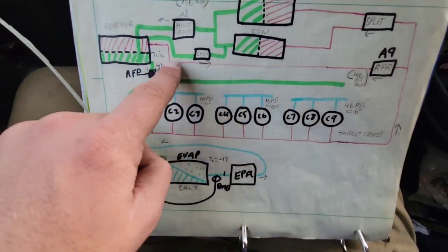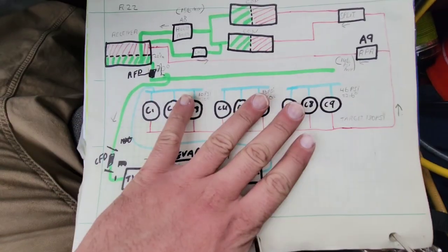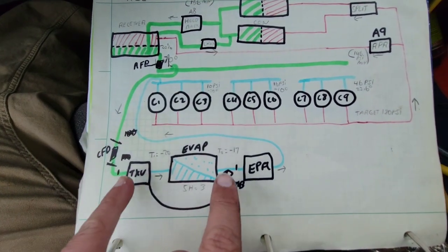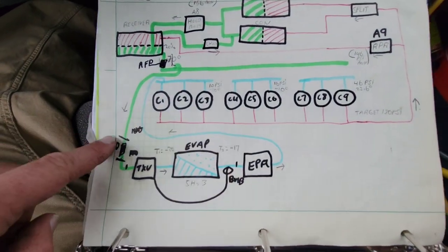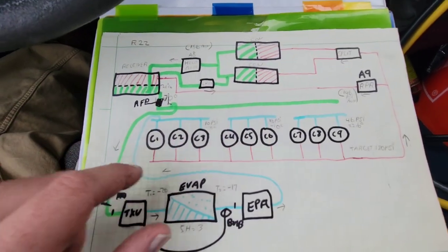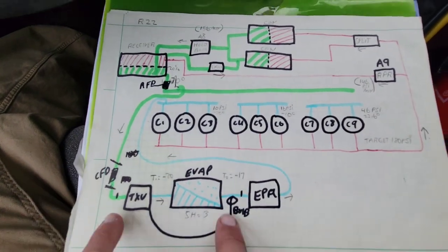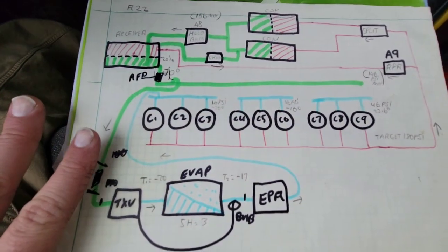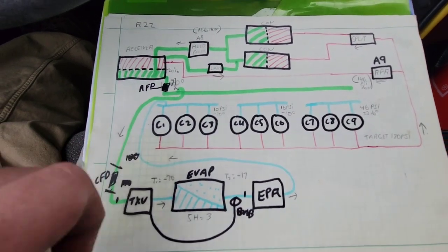So now, all right, next up, before we go to the filter dryer, I'm just interjecting this into the video because I got ahead of myself. We have to check the pressures at the rack and then the filter dryer. But actually, even before that, we have to check the hand valves. This step is kind of all done in conjunction. Filter dryer, pressures, and hand valves are all done together in a way. But in my opinion, the linear order is pressure, hand valve, and then filter dryer.